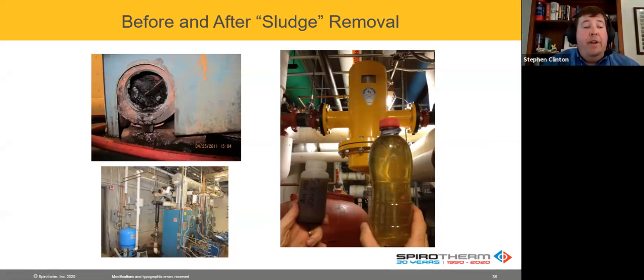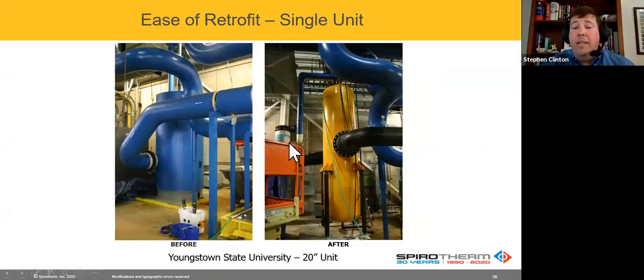So we remove air, we remove dirt. Now, some of you are in different parts of the industry, and one thing I'll encourage you to do is think about this for a retrofit application. This is at Youngstown State University. They'd done a performance contract, no air separator originally. After the performance contract, new chillers, variable primary, everything should have been working great. They were still having issues in a system that was over a mile long. Over a long weekend, they took this unit out and installed our unit. That's the only change they made. Everything was clean, everything was operational.